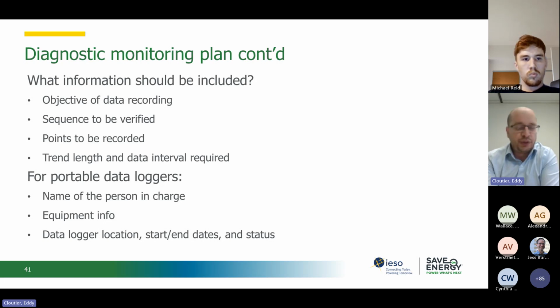Obviously, if we want the recorded data to be meaningful, we must ensure that the measuring equipment is, I would say, reasonably calibrated. And it's true also for the BAS system sensors. If you're trying to analyze your monitoring with insufficiently calibrated BAS sensors, you will probably not reach the correct conclusion in your analysis.